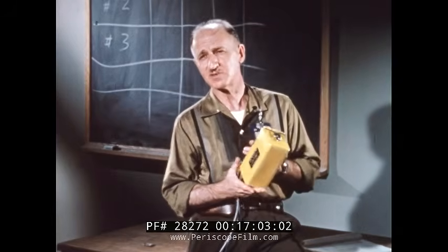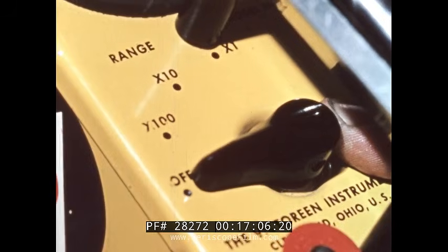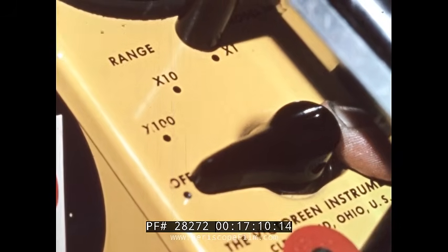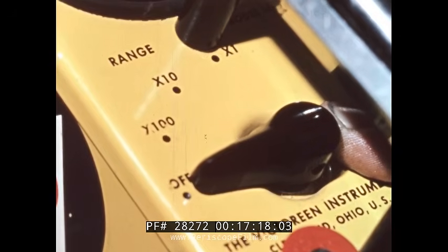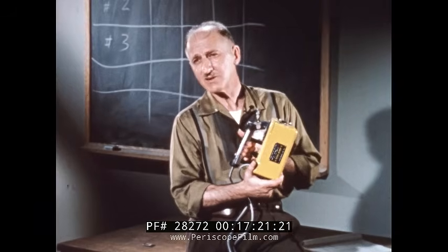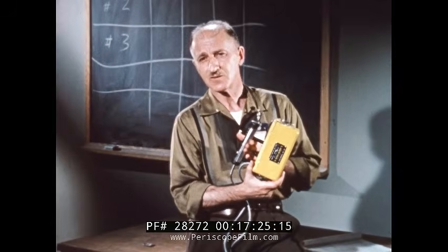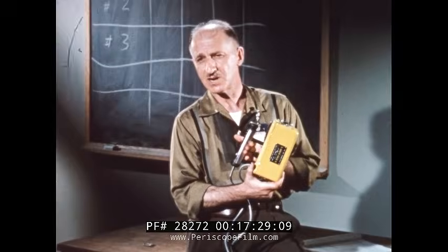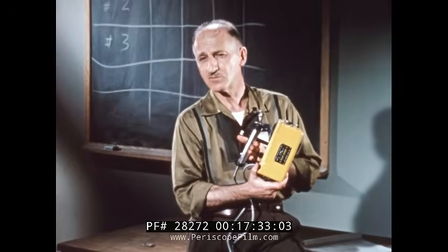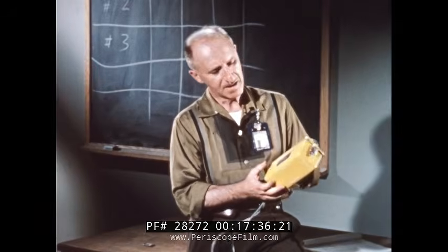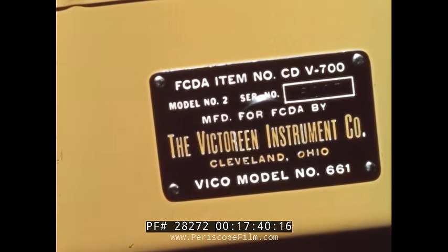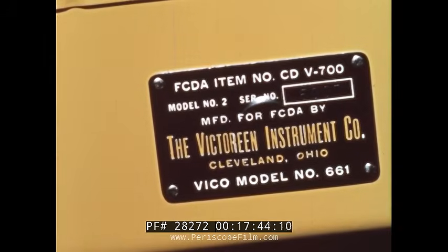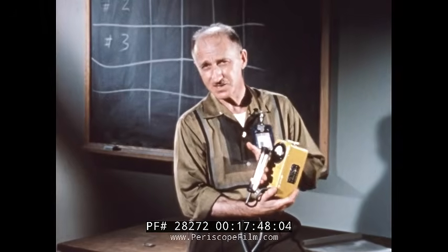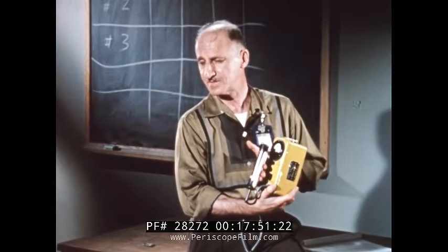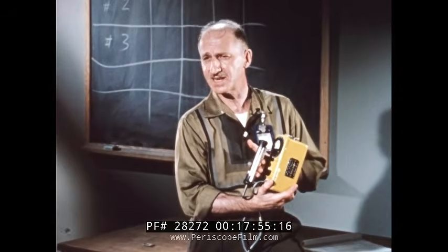3 ranges of operation are provided. The ×1 scale requires 500 pulses per minute for full-scale operation. The ×10 scale, 5,000 pulses, and the ×100 scale, 50,000 pulses per minute. In terms of milliroentgens, these readings correspond to 5/10 MR per hour, 5 MR per hour, and 50 MR per hour of radium equivalent radiation. On the side of the instrument, just beneath the nameplate, a beta source is provided for checking the operating capability of the instrument. Because of its low range, the CDV 700 is essentially a training instrument. In addition, however, it is useful in personnel and vehicle monitoring.